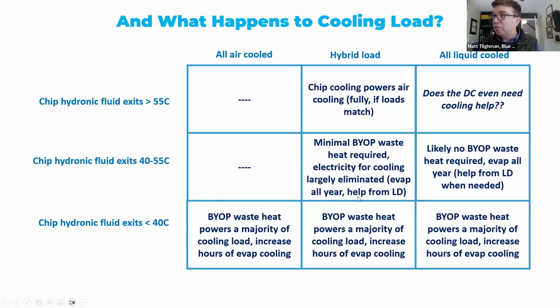But for hybrid loads where you have chip cooling and air cooling, the chip cooling can now power the air cooling. You can regenerate the desiccant with the warm water that's used for the chip cooling and use that desiccant to eliminate the air cooling load or shift it towards evaporative cooling all year long.